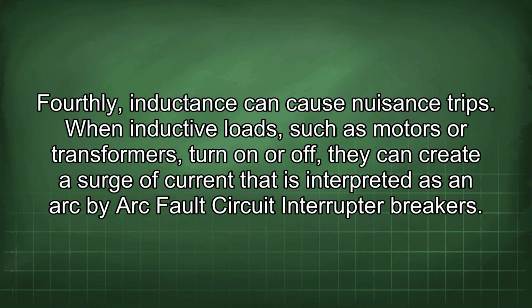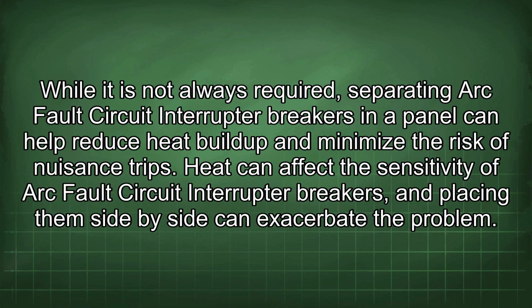Fourthly, inductance can cause nuisance trips. When inductive loads, such as motors or transformers, turn on or off, they can create a surge of current that is interpreted as an arc by arc fault circuit interrupter breakers. While it is not always required, separating arc fault circuit interrupter breakers in a panel can help reduce heat buildup and minimize the risk of nuisance trips.